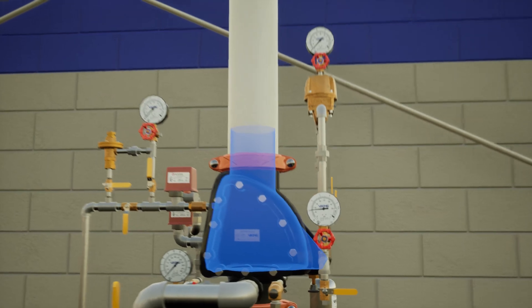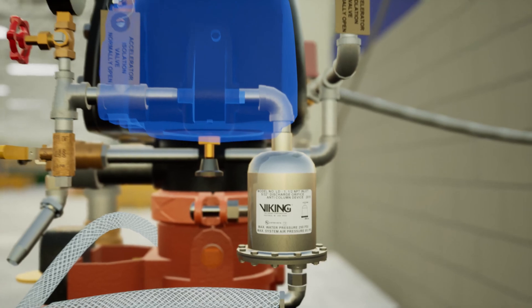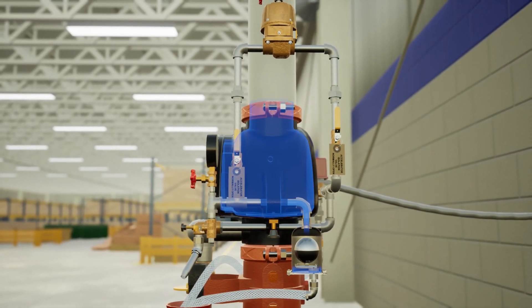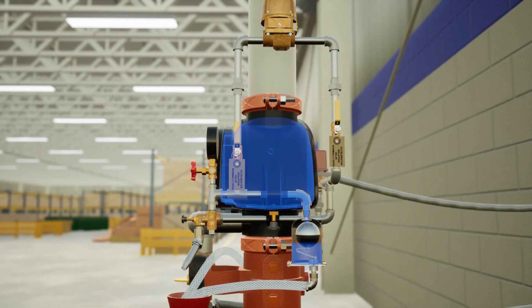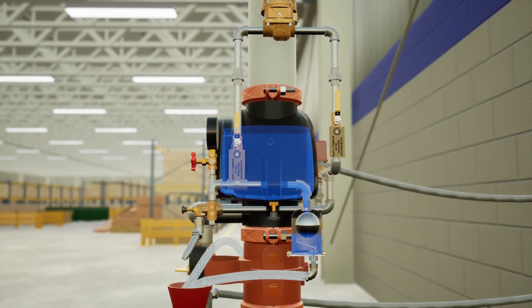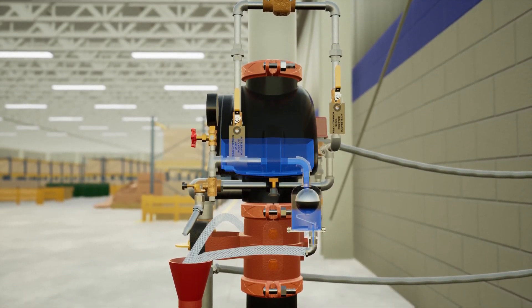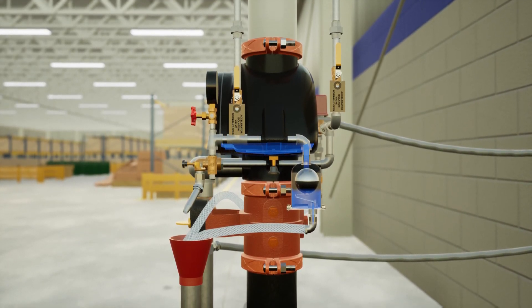However, an anti-column device will prevent this from occurring. The hollow steel ball inside of the anti-column device acts as both a weight and a buoy. If water is present, it will float to the top, allowing water to drain out the bottom. Otherwise, it will return to its resting position, resealing the chamber.